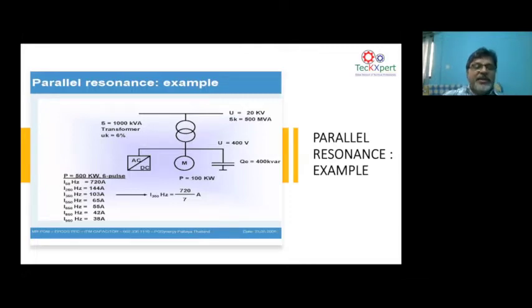As you know, the rated current, we all know, √3 VL IL cos phi gives you the fundamental current. But then to calculate the 250, 350, 650, you divide by that particular magnitude. As I told you before, in the Fourier transformation, the higher frequency goes by the division of its magnitude. For example, if you want to see the 5th harmonic, 720 divided by 5, you get a number which is near to that 144. And so like that, the harmonic calculations are done at the respective harmonic current. So here, if you see, when you have a resonance taking place near to the 7th harmonic, you have 103 amps flowing in the network. Go to the next slide.